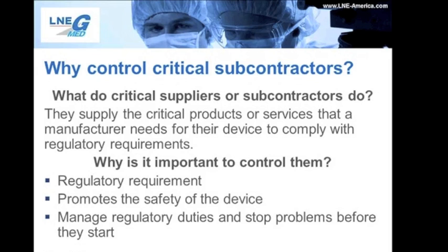For example, looking at your sterilizer, if you don't exercise at least a modicum of control over them, how do you know if your devices are actually being sterilized? This question has some pretty big implications for device and patient safety that a manufacturer would be on the hook for answering. Finally, by continuously exercising control over their subcontractors, manufacturers can manage their regulatory duties and stop problems before they start.